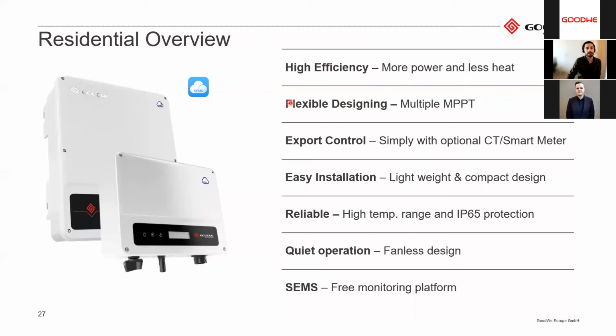To summarize the residential portfolio: they have high efficiency, giving more power and less heat. You have a flexible design with multiple MPPTs, both for single-phase and three-phase. You have export control, either connecting the CTs or the smart meter. They're also very lightweight and compact, which makes them easy to transport and easy to install. They all work up to 60 degrees Celsius and have IP65 protection, so you can install them both inside and outside. They have quiet operation with a fanless design up to 6 kilowatts. And all of our products include SEMS, which is free, not only for residential but for our whole portfolio.